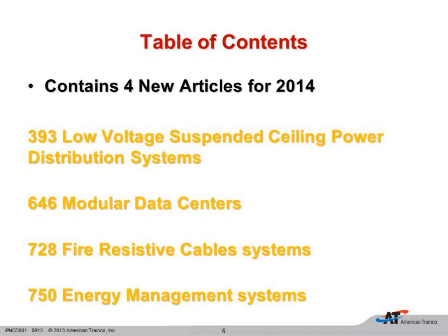These are low voltage suspended ceiling distribution systems. They are going to operate right around 30 volts AC or less, or 60 volts DC or less. The one that I've seen so far was 24 volts DC. It has to be listed as a complete system. It's going to come with its own utilization equipment, so the lights that are going to be mounted to this ceiling grid will come with it. The power supply will come with it.